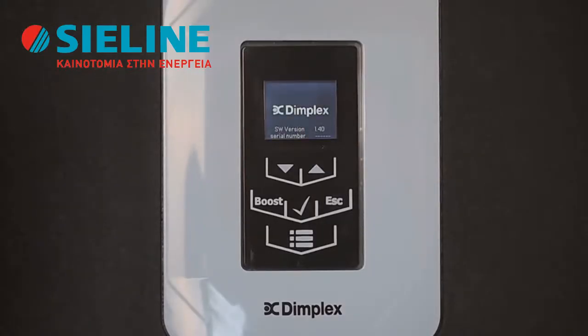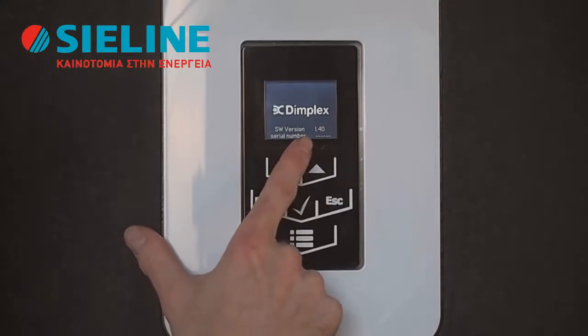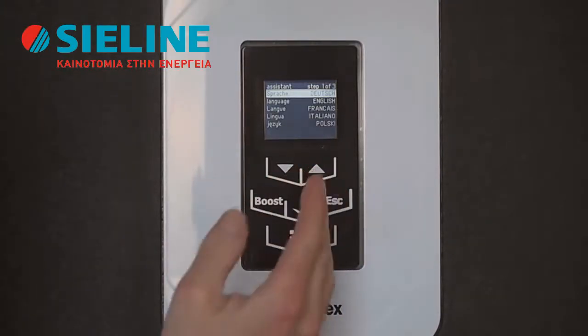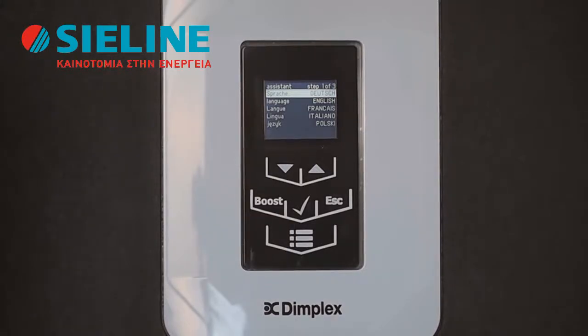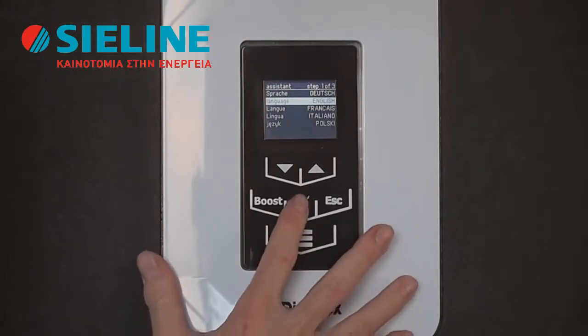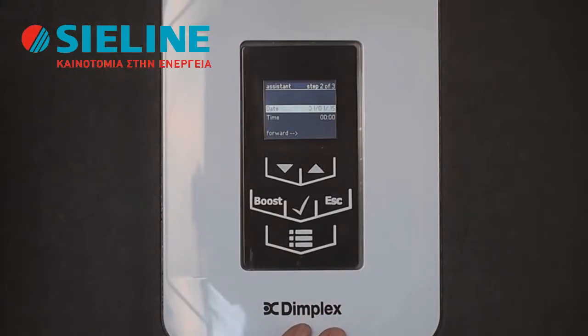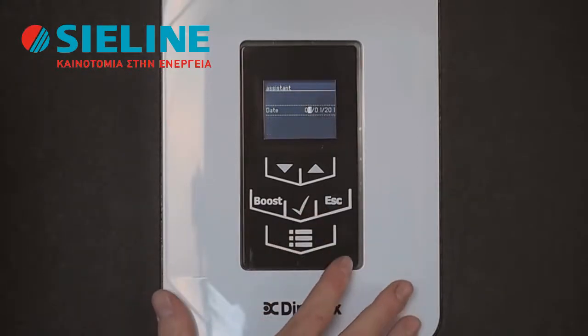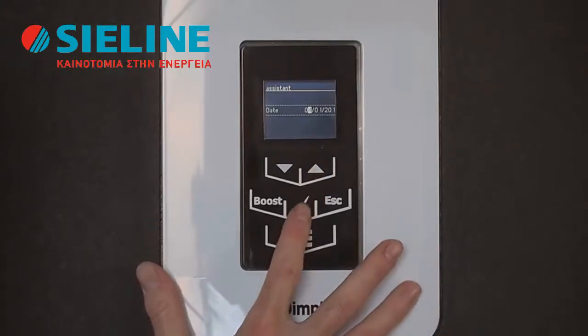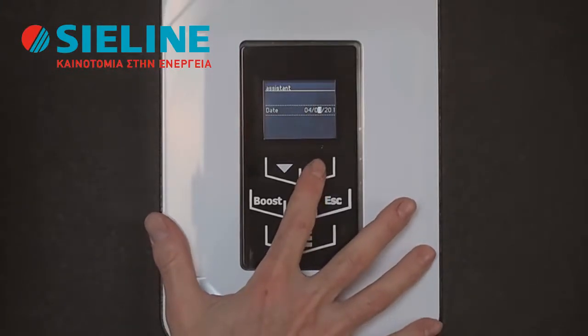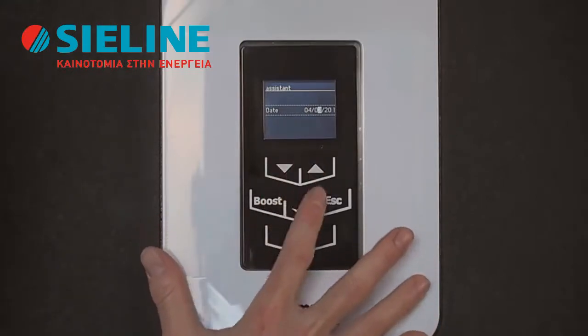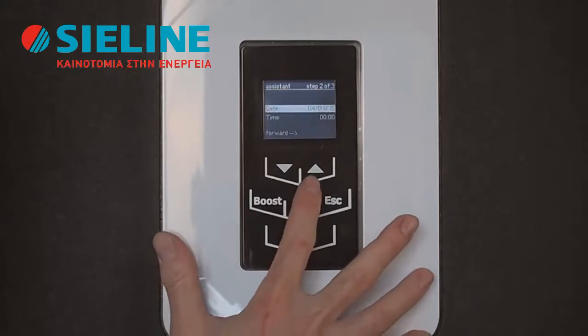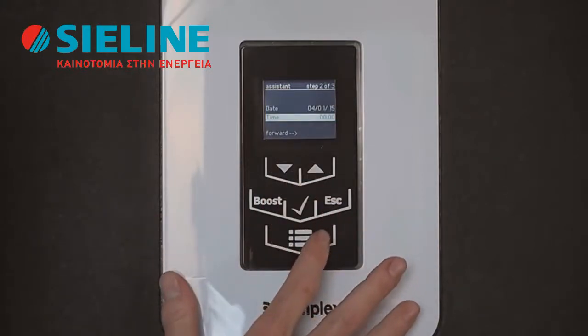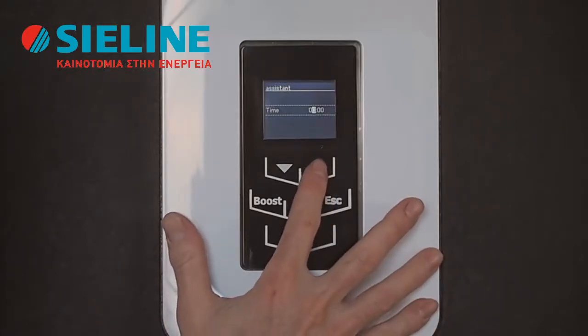When plugging in the heat pump for the first time, the commissioning menu starts automatically. First of all, you have to make a choice for your language. Please use the arrow up and down buttons and confirm with the tick off button. Next, you have to make a setting for the current date and time. Again, simply use the arrow up and down buttons and confirm with the tick off button. Same you do for the time.